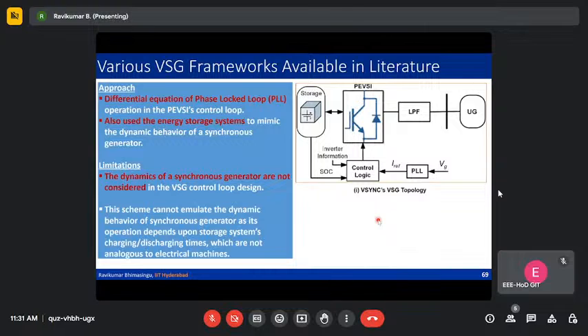It uses a PLL, which is a differential equations based PLL, used in the operation of the power based voltage source inverter control loop. It also uses energy storage systems to mimic the dynamic behavior of the synchronous generator. The limitation of this topology is that the dynamics of the synchronous generator are not considered in this VSG control loop design, so it cannot emulate the dynamic behavior of the synchronous generator, as its operation depends on the storage system's charging or discharging times, which are not analogous to electrical machines.